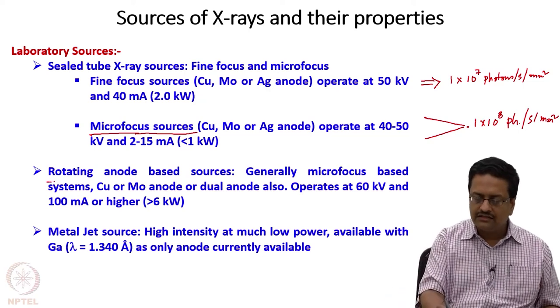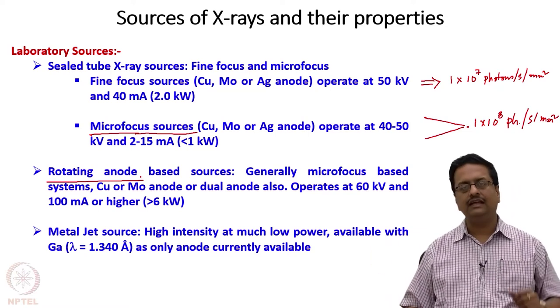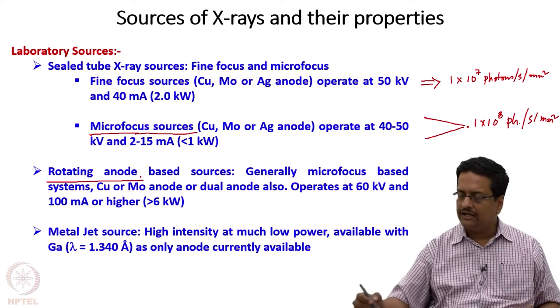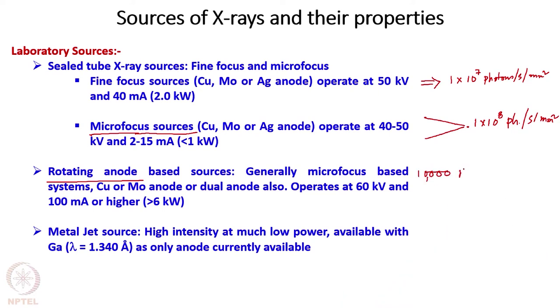The next higher intensity source is a rotating anode based source where the anode, which was fixed in the previous design, here rotates at very high speed at about 10,000 RPM. We can then use a much higher flux of electrons falling on the anode, which generates X-rays in the range of about 1×10¹⁰, sometimes even 10¹¹ photons per second per square millimeter. Micro focus rotating anode based sources can lead to enormously high energy on a crystal, reducing the data collection time to about 20 to 30 minutes.